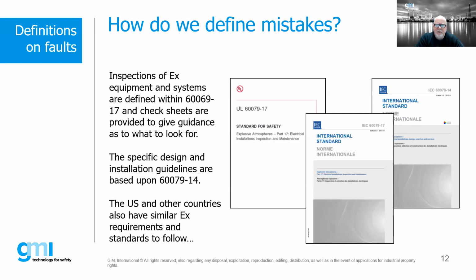I always recommend skid package builders and manufacturers take a look at that, because within the -17 standard there are actually some really good EX checklists to make sure that when you're doing your FATs, your final inspections before you ship out to the customer, that you've done all your due diligence. So we're going to see some of those types of issues.